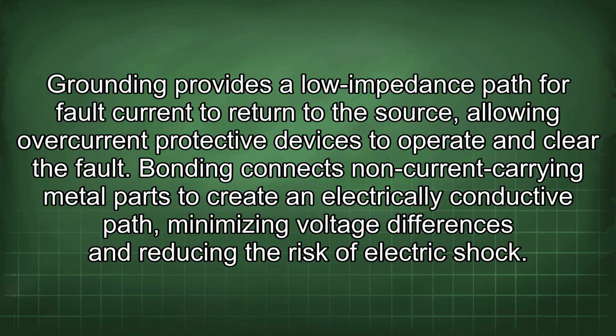Grounding provides a low impedance path for fault current to return to the source, allowing overcurrent protective devices to operate and clear the fault. Bonding connects non-current carrying metal parts to create an electrically conductive path, minimizing voltage differences and reducing the risk of electric shock.